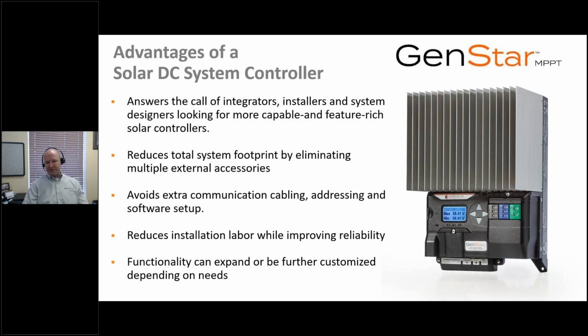It reduces total system footprint because you don't have this whole array of DIN-rail mounted equipment. You've got a very compact amount of control integrated using the ready blocks, which I'll talk about shortly, on the right side of the product. With a massive amount of capacity, this controller can handle up to 5,000 watts of continuous power delivery, and we have the ability to oversize it up to 150%.